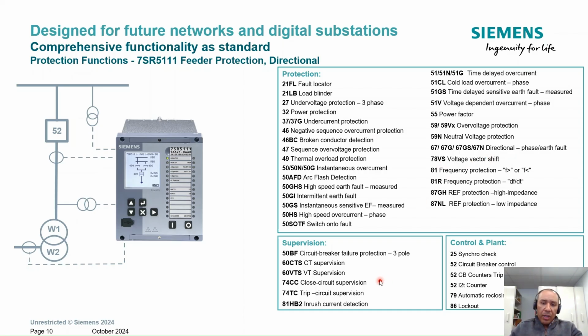The same supervision as mentioned before, the control as well, is possible. There is one option on this device where you can have a fifth CT input, okay, and this device then cannot perform transformer protection.